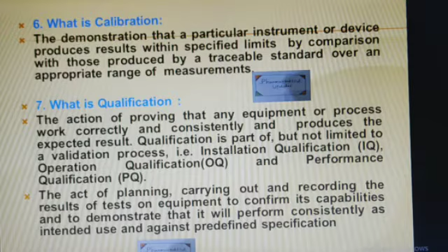What is qualification? The action of proving that any equipment or process works correctly and consistently and produces the expected result. Qualification is part of but not limited to a validation process, that is installation qualification IQ, operational qualification OQ and performance qualification PQ. The act of planning, carrying out and recording the results of tests on equipment to confirm its capabilities and to demonstrate that it will perform consistently as per intended use and against predetermined specification.